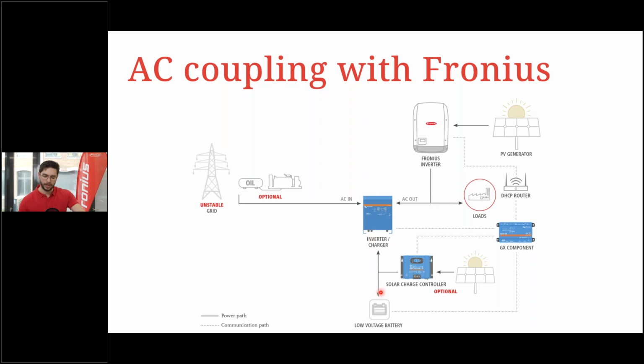For example, you have the possibility to integrate a low voltage battery here. Then the option would be to connect a solar charge controller from Victron with a few modules connected onto that in order to have a better charging efficiency rate, because in this case we would charge from those modules directly from DC to our batteries, and not from the Fronius inverter DC to AC, AC to DC to the batteries. So a few options are possible for you.